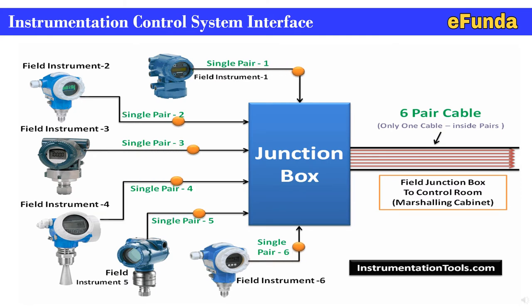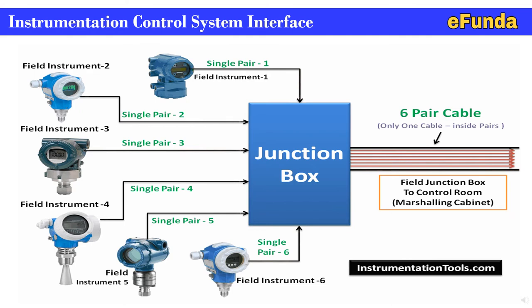For instrumentation control system interface, a figure from instrumentationtools.com shows various field instruments connected to junction boxes and further connected to the control room. Field instruments 1 through 6 each have a single pair cable connected, and in the junction boxes all cables are consolidated — six pairs in one cable — connected to the control room so as to carry the signal of each of the six field instruments to the control room for further control room engineering.